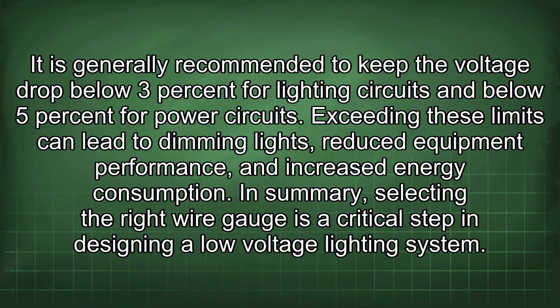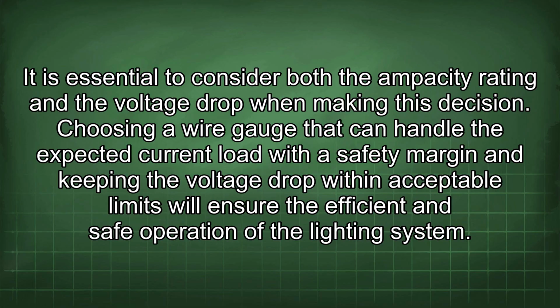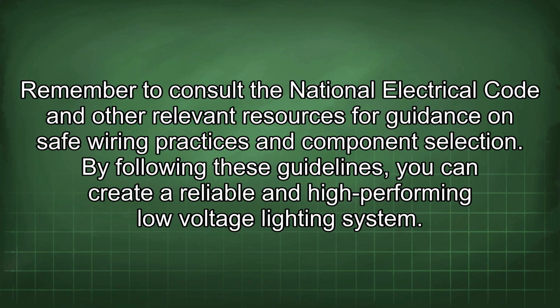In summary, selecting the right wire gauge is a critical step in designing a low-voltage lighting system. It is essential to consider both the ampacity rating and the voltage drop when making this decision. Choosing a wire gauge that can handle the expected current load with a safety margin and keeping the voltage drop within acceptable limits will ensure the efficient and safe operation of the lighting system. Remember to consult the National Electrical Code and other relevant resources for guidance on safe wiring practices and component selection. By following these guidelines, you can create a reliable and high-performing low-voltage lighting system.